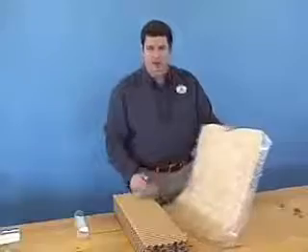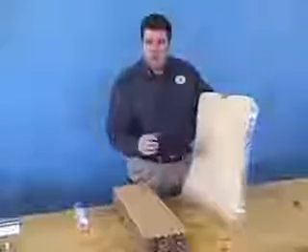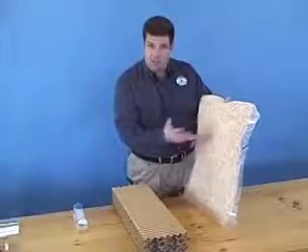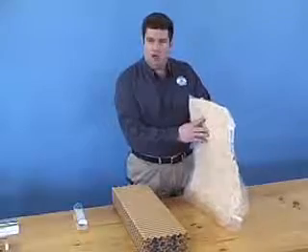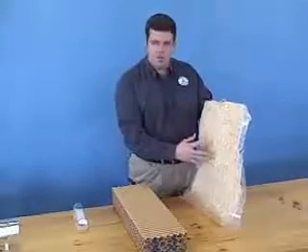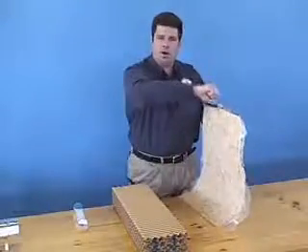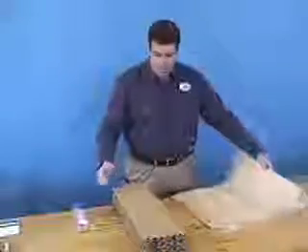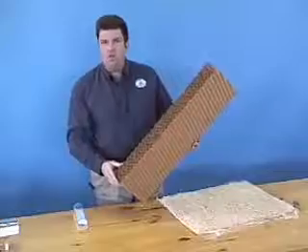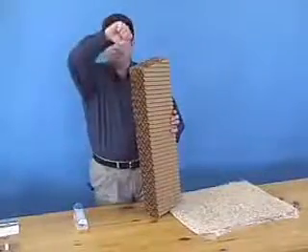Swamp cooling has been around for thousands of years. You simply blow air over a wetted surface so that the air evaporates water off the surface and into the airstream. Common residential swamp coolers blow air through shredded aspen trees contained in a mesh and wetted by continuously pouring water from above. Commercial and some residential swamp coolers use a corrugated cardboard system instead of aspen trees, which works in a similar fashion.